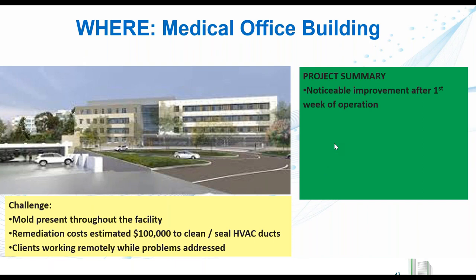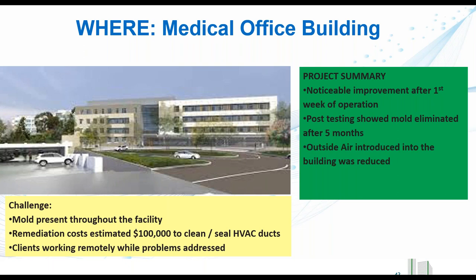The summary for this: there was a noticeable improvement after the first week of operation of the needlepoint bipolar ionization equipment. Five months later, post-testing showed the mold was eliminated. The outside air that was introduced in the building was reduced, and there was a small energy savings that resulted from that of $12,500.